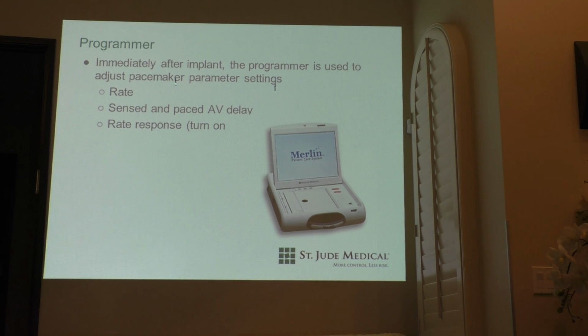Things that can happen during the case that the rep watching would catch are that the atrial lead can fall out. It drops out of the atrium. The ventricular lead could pull back. Generally, it's the end of the line. It doesn't fall out of the ventricle, because it's being pushed down and gravity kind of wants it to go that way. Whereas the atrium, you're more anterior when the patient's lying supine. So if it falls, gravity's actually pulling it down, and the flow of blood going past it is pulling it away. Whereas the ventricle is just inclined to sit there.